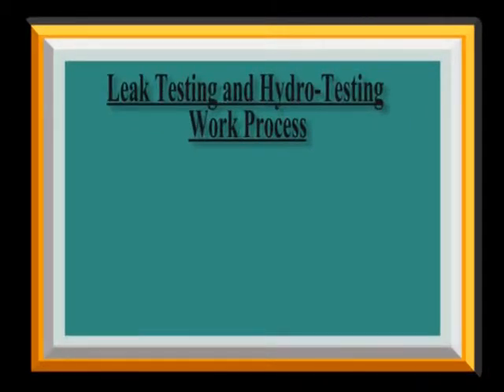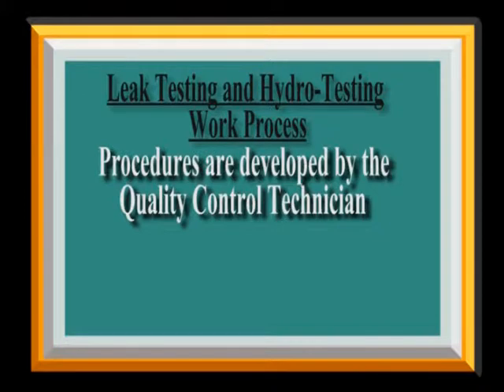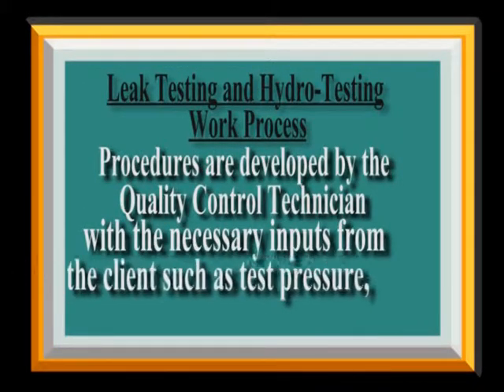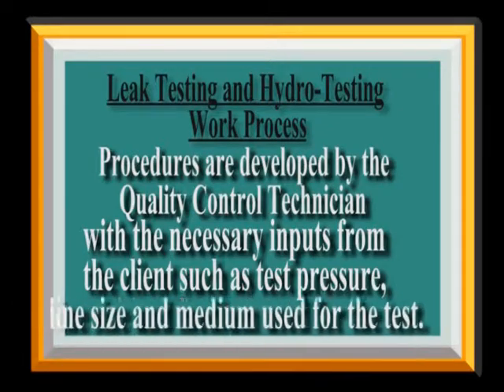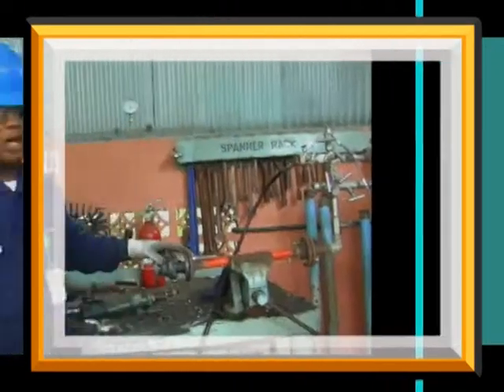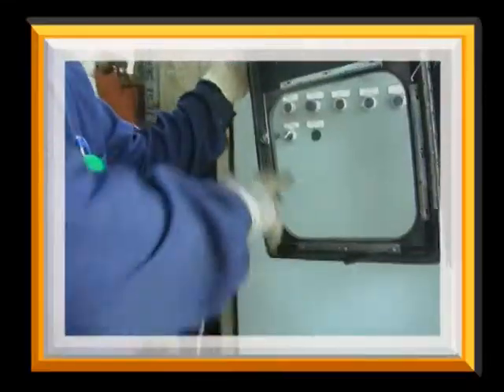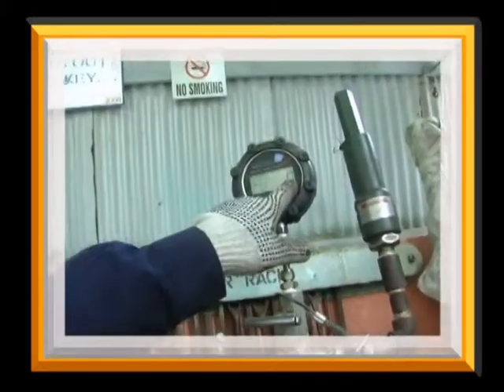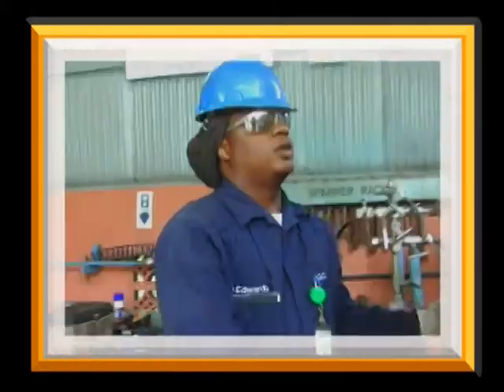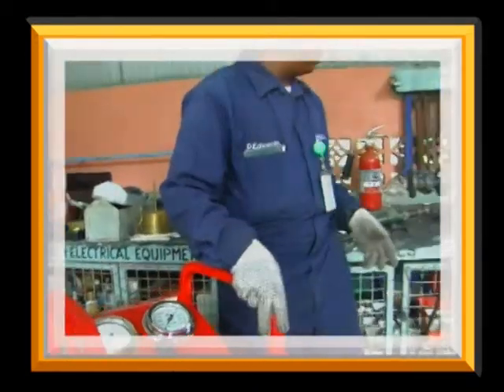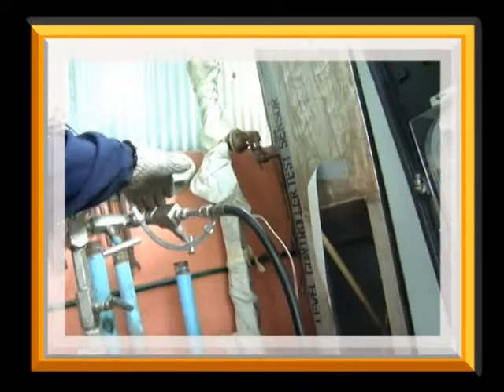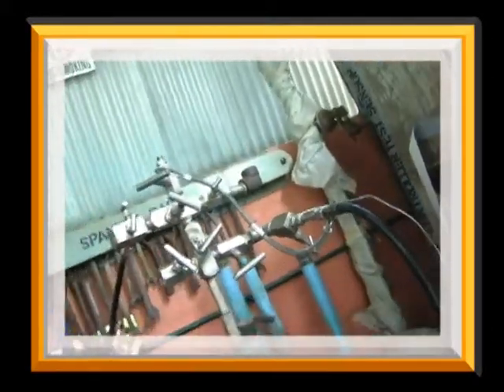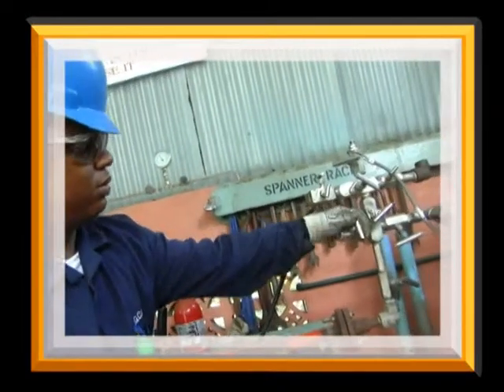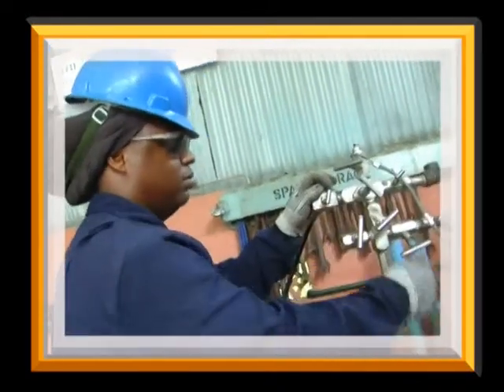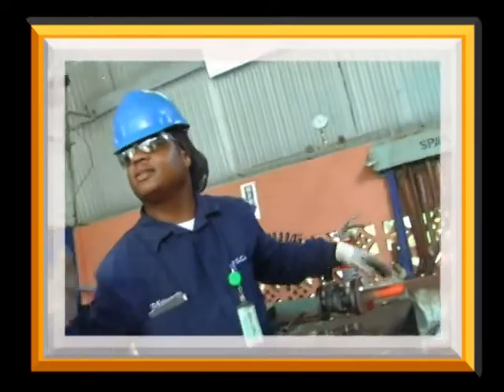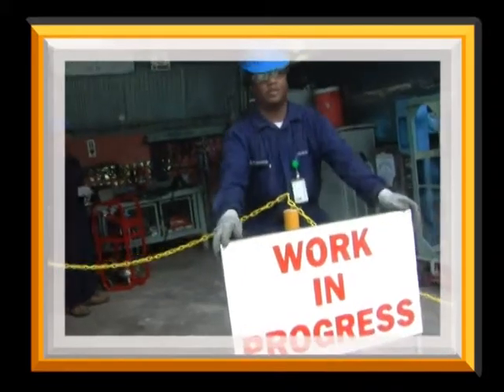Leak testing and hydro testing work process. Procedures are developed by the quality control technician with the necessary input from the client, such as test pressure, line size, and medium used for the test. Checks are made to ensure all our equipment certification is valid. All testing equipment is strategically placed and aligned to begin testing of the customer's item. Workers ensure that all adjoining systems have been isolated by blinding or venting to prevent any pressure buildup. All valves for freedom of movement are open and vents have been isolated or blanked.